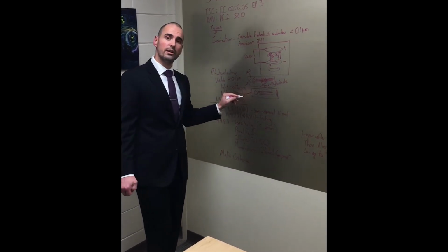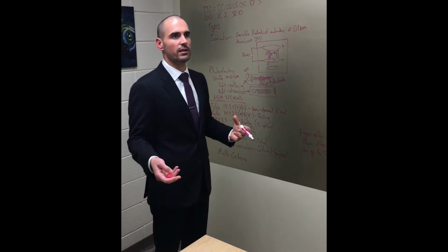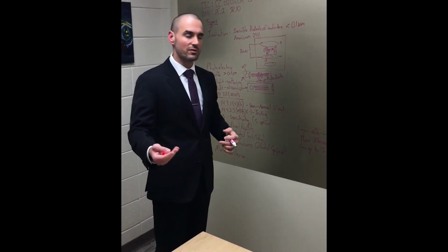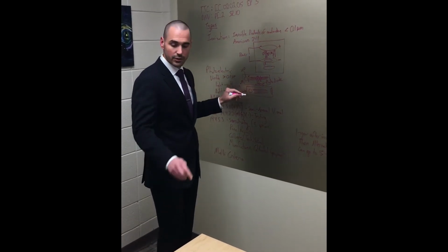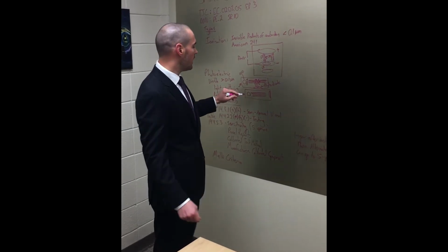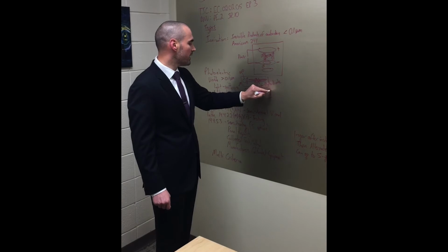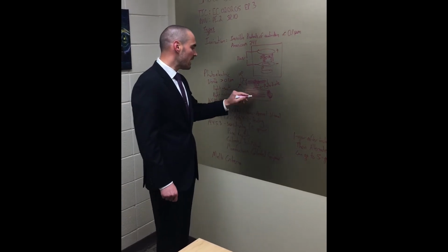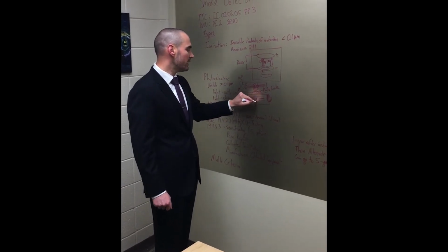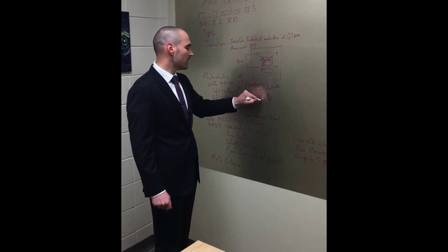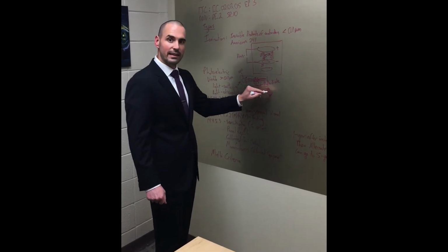Light obscuration is very similar. The best way to think about it is a beam detector in like your atriums and stuff like that. So they do have it for detectors, but that's how you think about it. It's got a beam, and over here is our photodiode. And when smoke enters, it actually starts blocking some of the light that hits that photodiode.